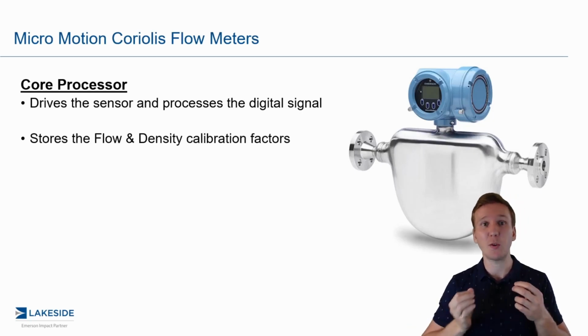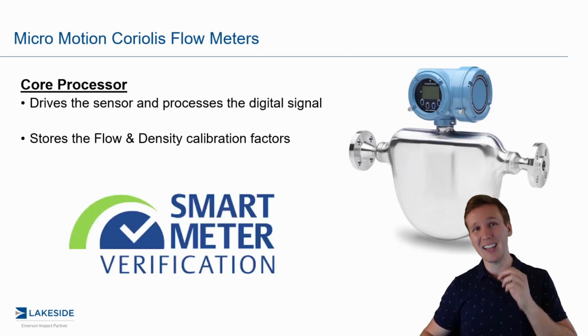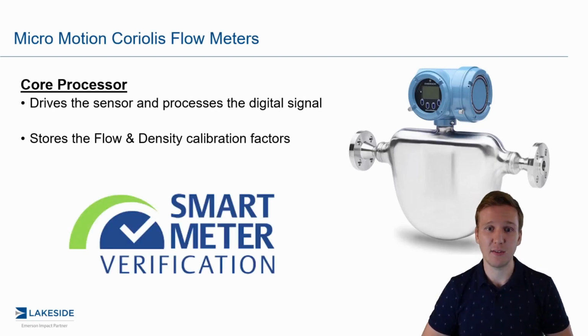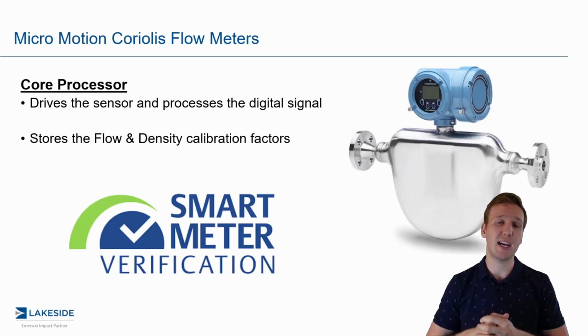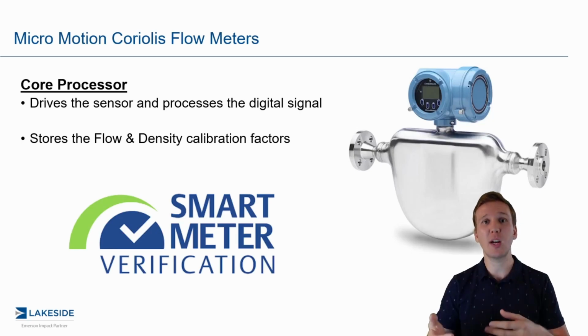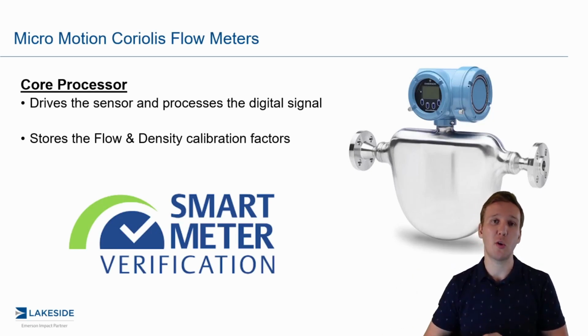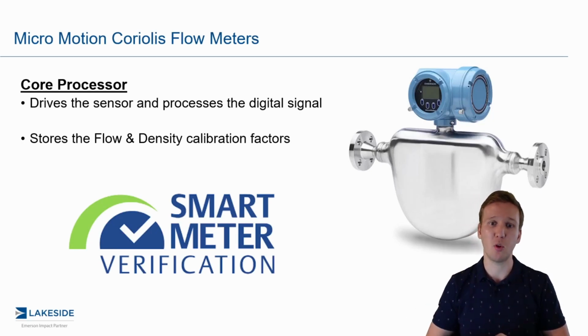Also, it stores our factory's flow and density calibration factors. So this is something that is very, very important to our Coriolis flow meters. And finally, it actually allows us to run our Smart Meter Verification features. So if you don't know what that is, be sure to check out a few episodes back. I talked all about SMV, a very, very important feature that is free and part of new Coriolis flow meters going forward. A very, very handy troubleshooting tool, a very, very handy tool to establish confidence in your Coriolis flow meter.